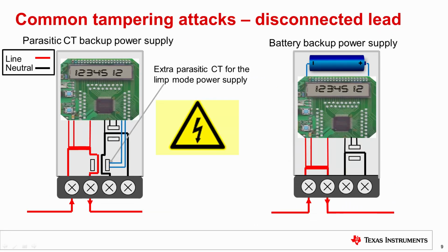Additionally, disconnecting a lead is one way a meter may be tampered. Limp or live-only mode allows the meter to function in a limited way with one lead completely disconnected. For this configuration, a parasitic CT can be used to extract the load power from the current flowing in the remaining connected lead for high current loads. This would work regardless of which lead is disconnected. Alternatively, a backup battery could be used to power the meter for this scenario. For metrology readings, since no voltage is available, the measured current is multiplied by the meter's nominal voltage to produce the measured power.